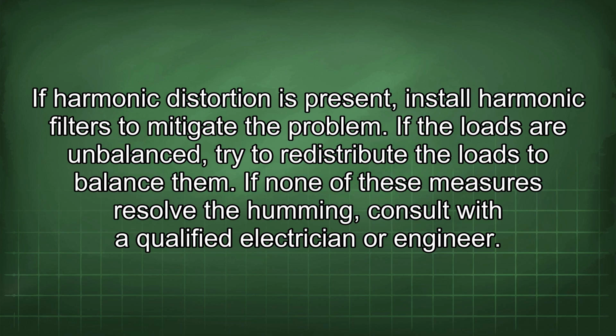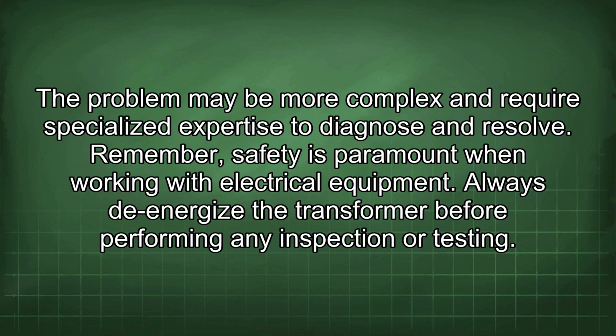If harmonic distortion is present, install harmonic filters to mitigate the problem. If the loads are unbalanced, try to redistribute the loads to balance them. If none of these measures resolve the humming, consult with a qualified electrician or engineer. The problem may be more complex and require specialized expertise to diagnose and resolve.